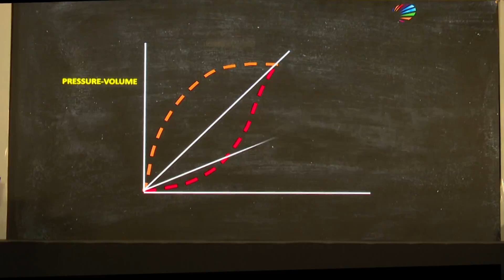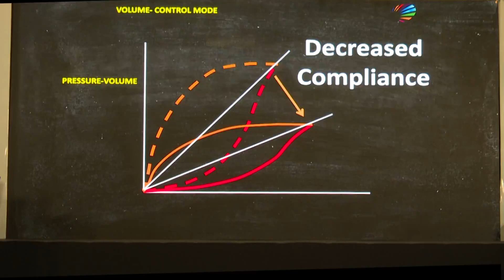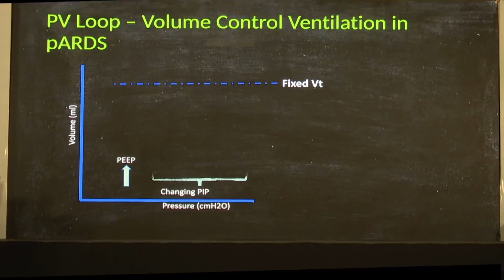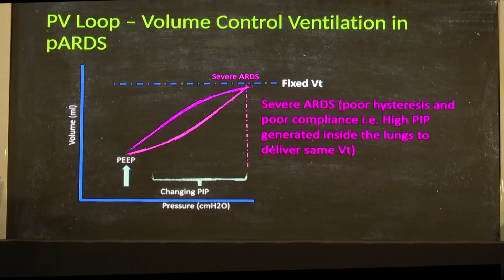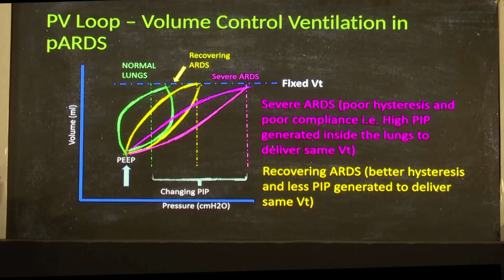The PV loop in volume control mode looks like this in a normal lung, and when the lung compliance is poor, it deviates towards the x-axis. We all know this. And in volume control mode, as we know, if the compliance is poor, the PIP or P plateau will be high and it will be more bending towards the x-axis. And as the compliance is improving, the PIP goes on reducing and the angle goes on becoming better and better. In pressure control mode, you cannot really assess the compliance, because as I said, the pressure is fixed.